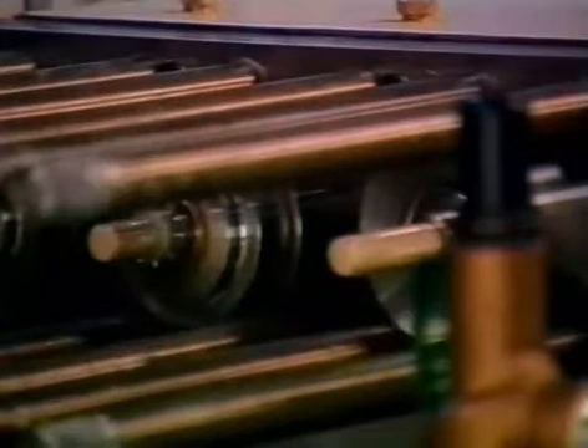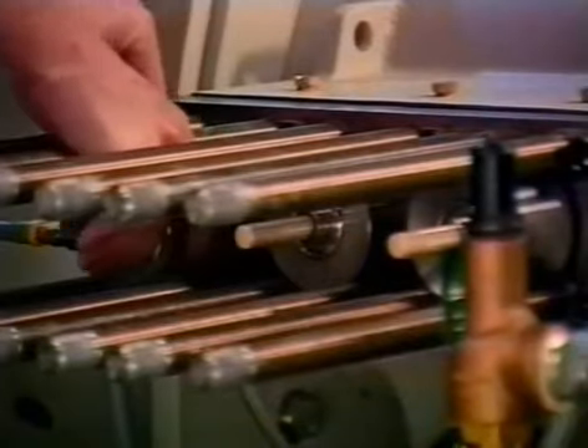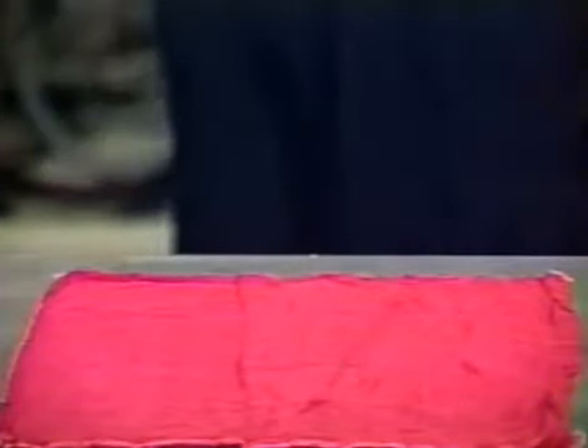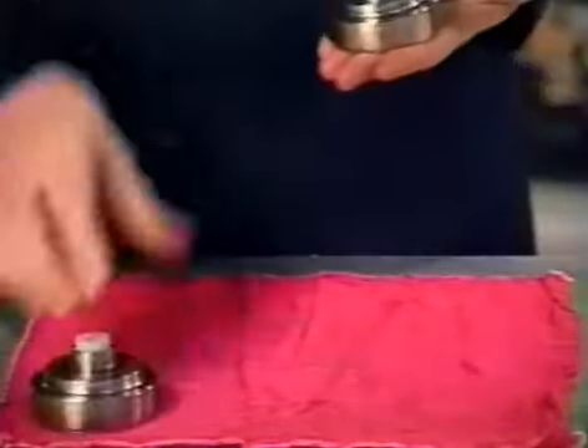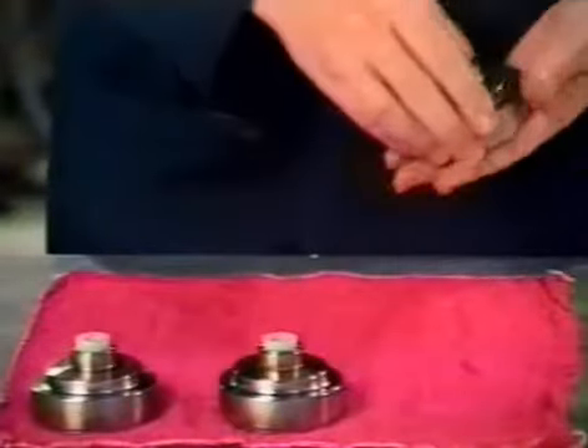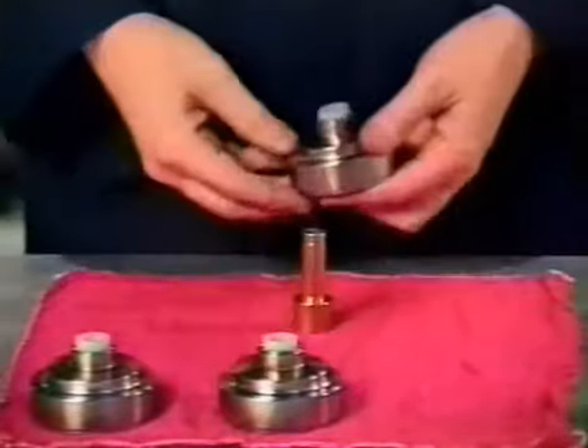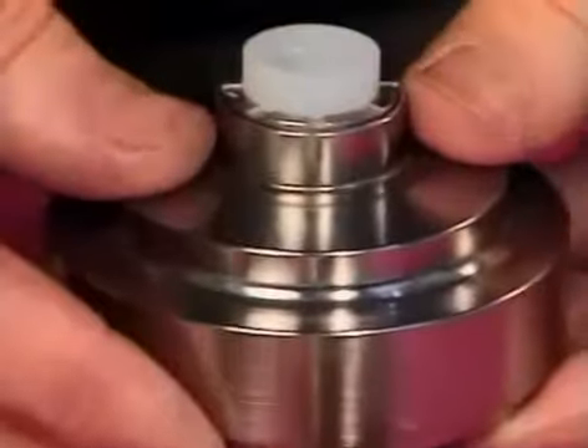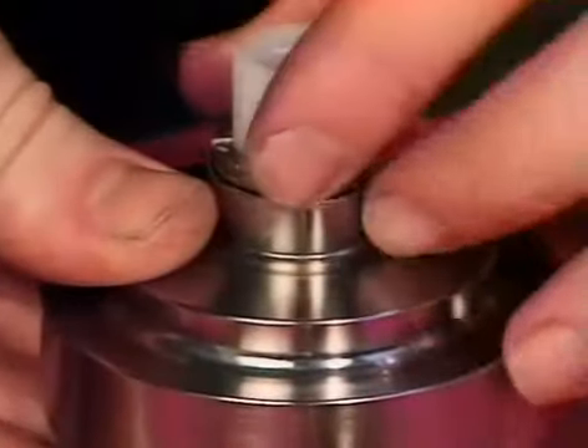Slide the backup ring housing off the plunger. Use the seal installation removal tool to remove the backup ring, dynamic seal, lip seal, and U-cup spacer from the backup ring housing.